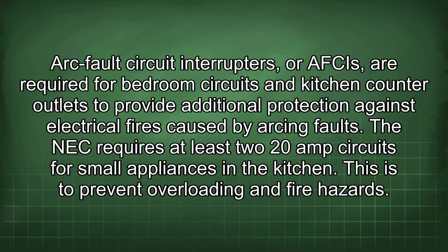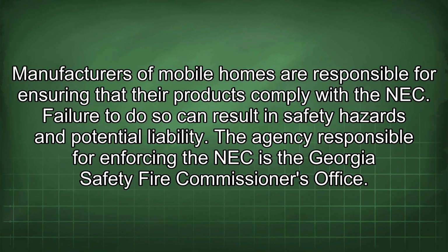Arc fault circuit interrupters, AFCIs, are required for bedroom circuits and kitchen counter outlets to provide additional protection against electrical fires caused by arcing faults. The NEC requires at least two 20-amp circuits for small appliances in the kitchen. This is to prevent overloading and fire hazards. Manufacturers of mobile homes are responsible for ensuring that their products comply with the NEC. Failure to do so can result in safety hazards and potential liability.